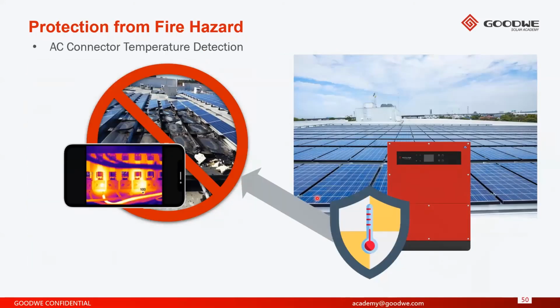So we have an option for fire hazard protection. For example, on the AC side, an installer or a customer can order the inverter with an AC temperature sensor at the AC output terminal, which measures the internal terminal temperature of the AC connector. And if the temperature of that terminal increases due to a short circuit because the cables aren't connected correctly, then the inverter will shut down if that internal temperature goes above a certain number of degrees.